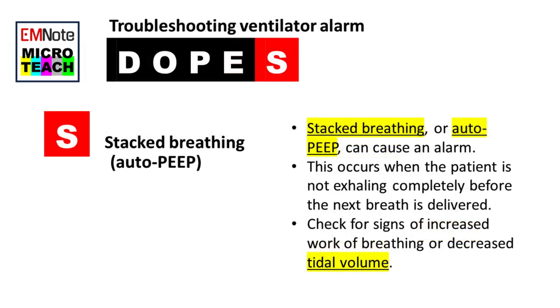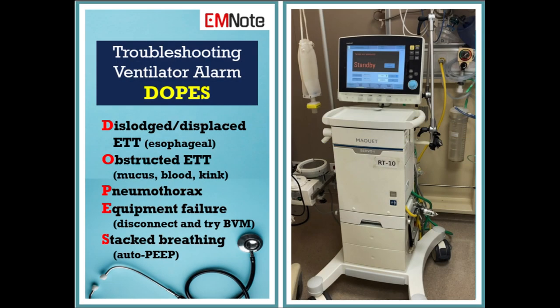S stands for stacked breathing, that is auto-PEEP. Stacked breathing, or auto-PEEP, can cause an alarm. This occurs when the patient is not exhaling completely before the next breath is delivered. Check for signs of increased work of breathing or decreased tidal volume.